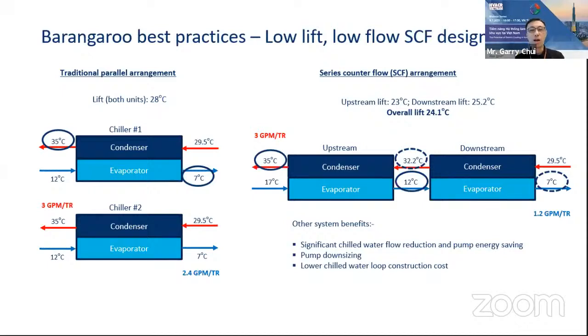Because of the use of the wide delta T, if you look into the chilled water supply circuit on the evaporator side, with this wide delta T of 10 degrees C, you can significantly reduce the pump flow by 50% compared to the parallel arrangement. So that helps a lot in terms of the reduction of your chilled water pumping energy, and it also provides the opportunity to downsize your pumping equipment.